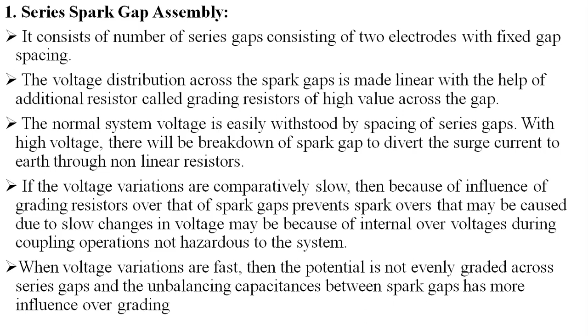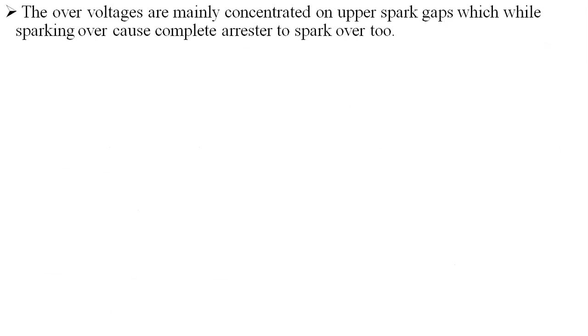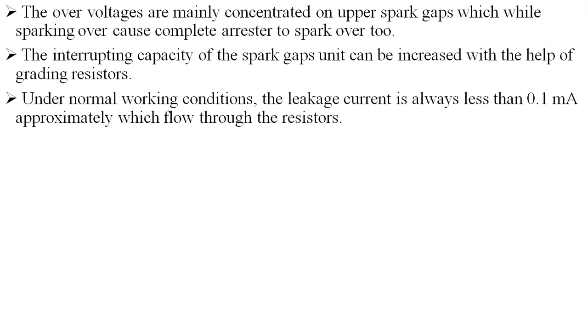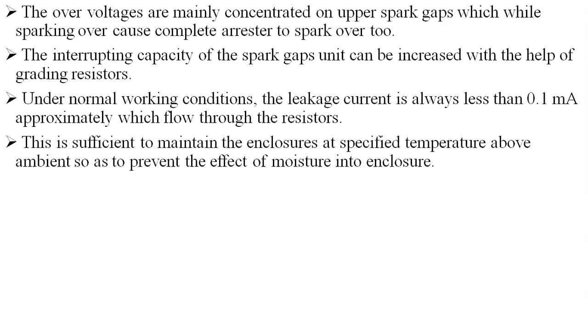When the voltage variations are fast, then the potential is not evenly graded across the series gaps, and the unbalancing capacitances between the spark gaps have more influence over grading. The over voltages are mainly concentrated on the upper spark gaps, which while sparking over cause complete arrester sparkover. The interrupting capacity of the spark gap unit can be increased with the help of grading resistors. Under normal working conditions, the leakage current is always less than approximately 0.1 milliamps, which flows through the resistors. This is sufficient to maintain the enclosures at a specified temperature above ambient so as to prevent the effect of moisture in the enclosures.